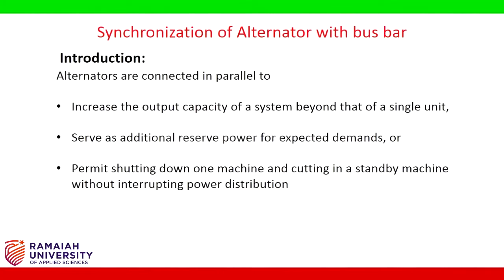Introduction. Alternators are connected in parallel to increase the output capacity of a system beyond that of a single unit. It serves as additional reserve power for expected demands or permit shutting down one machine and cutting in a standby machine without interrupting power distribution.